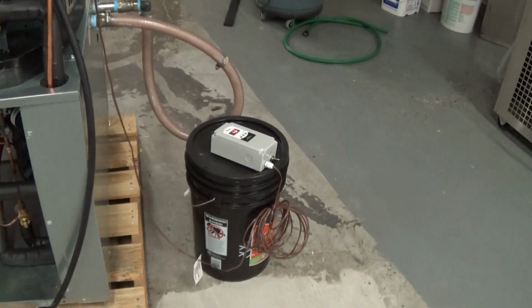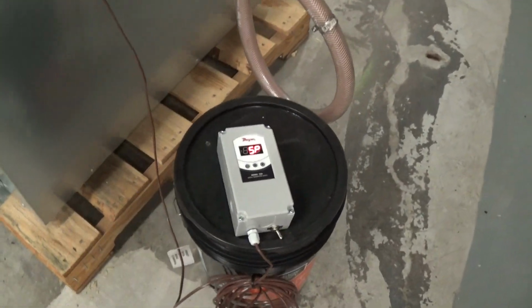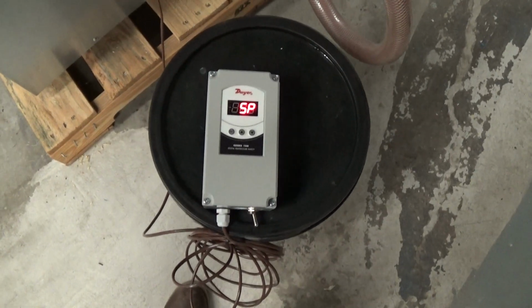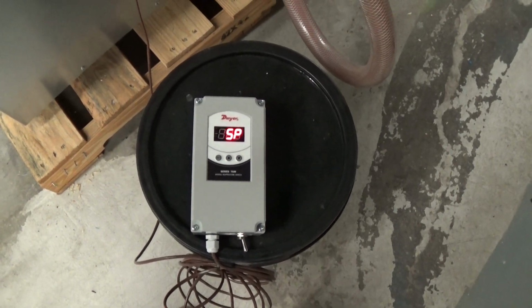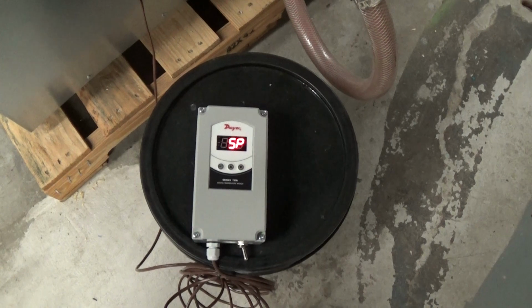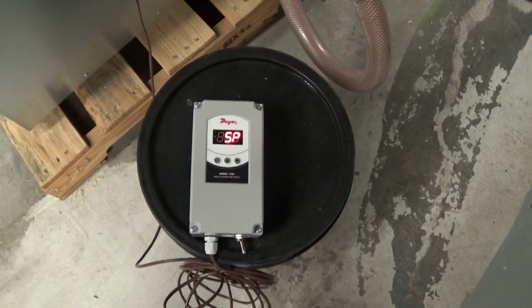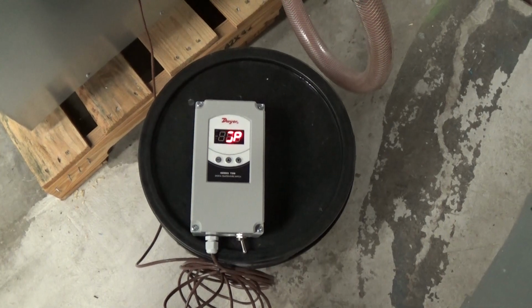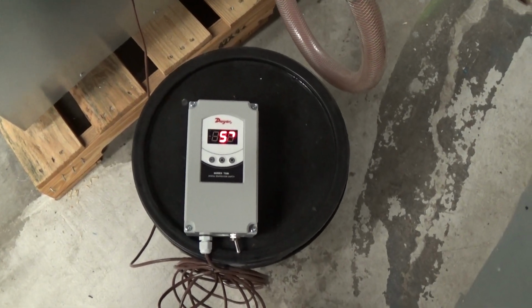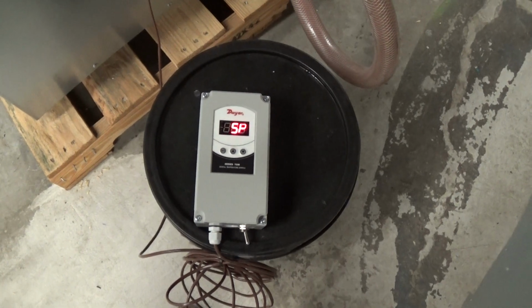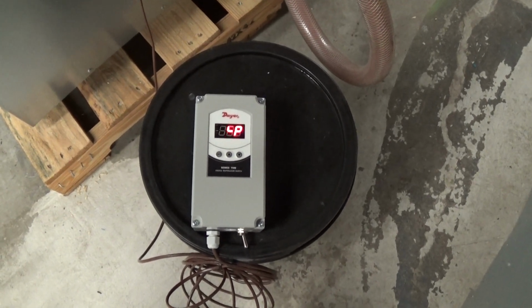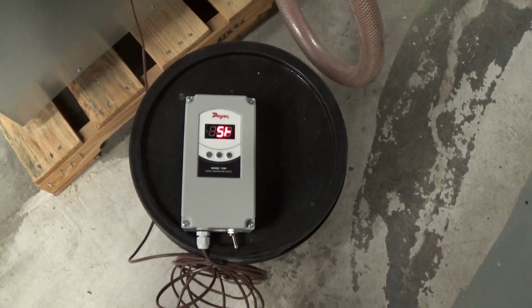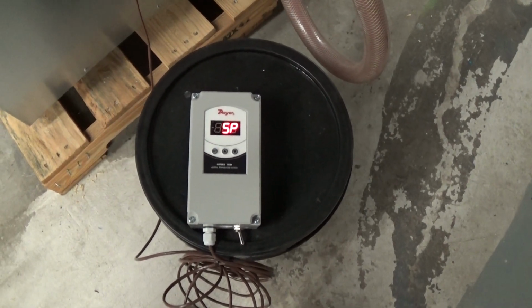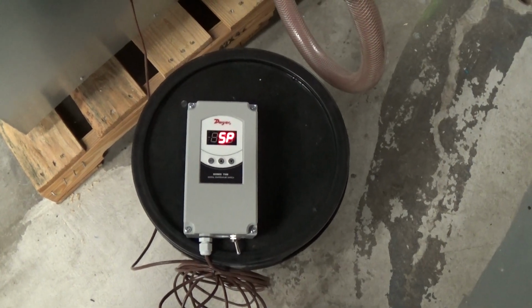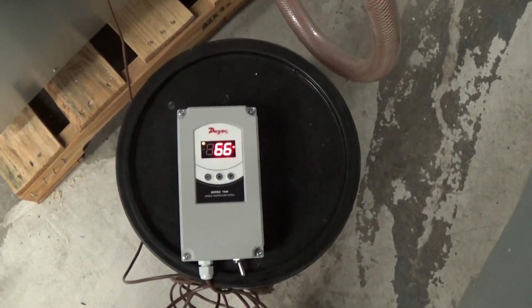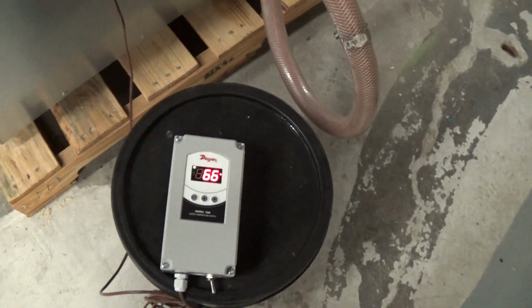So the differential that the controller comes with, this should default back to the temperature reading shortly. It comes with a 7-degree differential preset at the factory. So that means with our set point at 44 degrees, we're going to stop at 44, or the compressors and fans are going to stop. The pump always runs, and the unit's not going to turn the compressor back on until we're 7 degrees above set point, or 51. And you can see this defaulted back to our temperature.